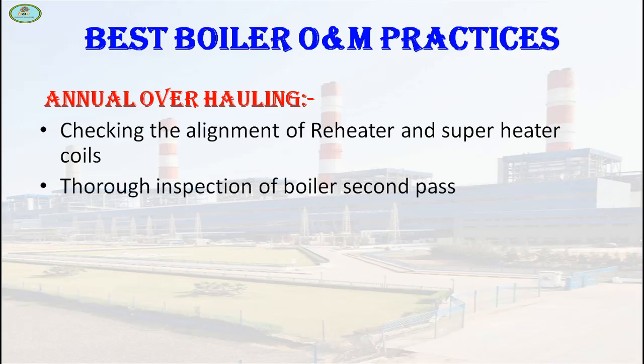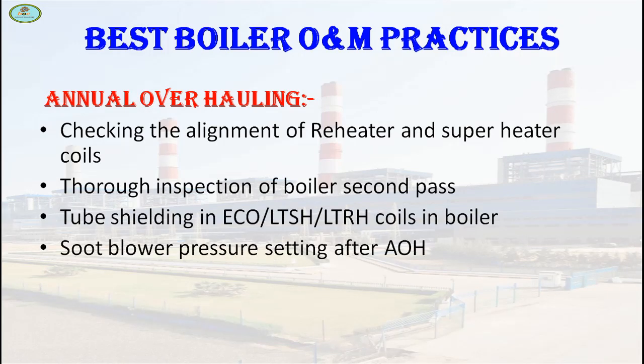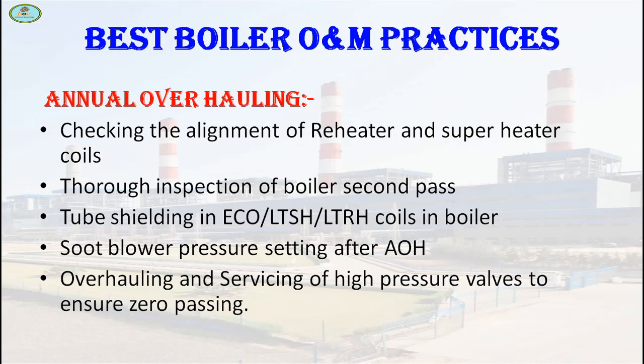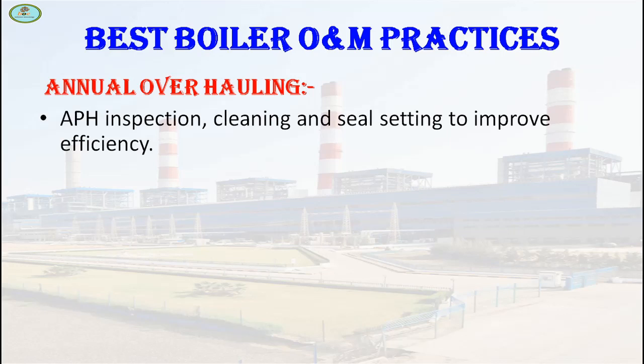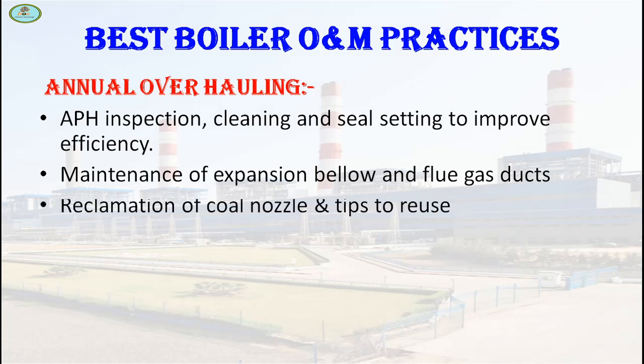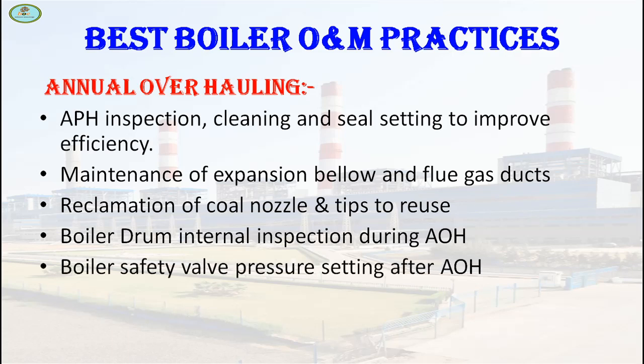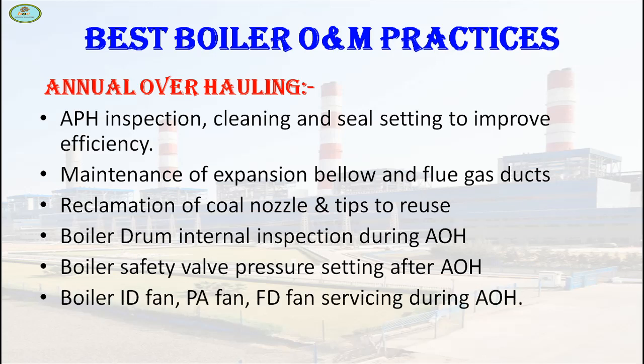Next one is annual overhauling. Activities include checking the alignment of reheater and superheater coils, thorough inspection of boiler second pass tube shielding in economizer, superheater, and reheater coils. Also, soot blower pressure setting after overhauling, overhauling and servicing of high pressure valves to ensure zero passing, APH inspection, cleaning and seal setting to improve boiler efficiency, maintenance of expansion bellows and flue gas ducts, reclamation of coal nozzles and tips for reuse, boiler drum internal inspection during annual overhauling, boiler safety valve pressure setting after annual overhauling, and servicing of boiler ID, PA, and FD fans during annual overhauling.